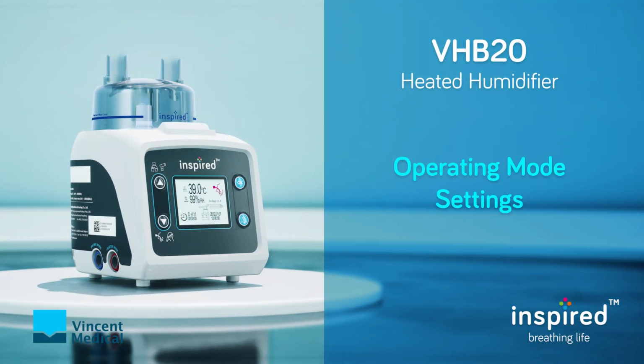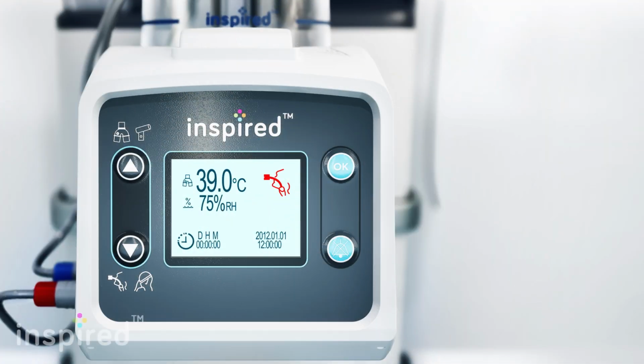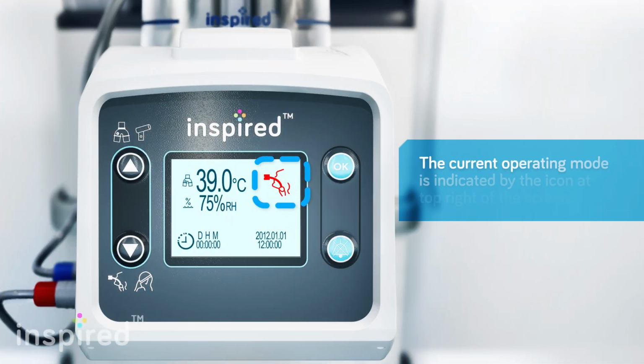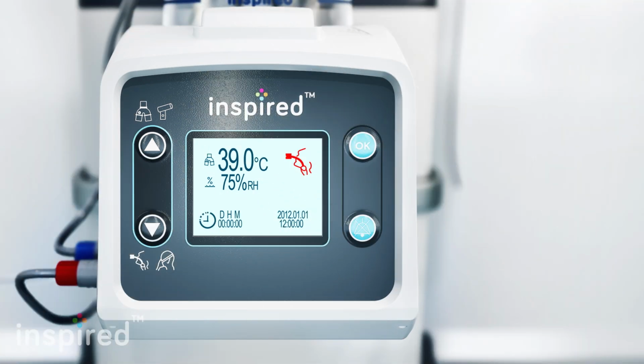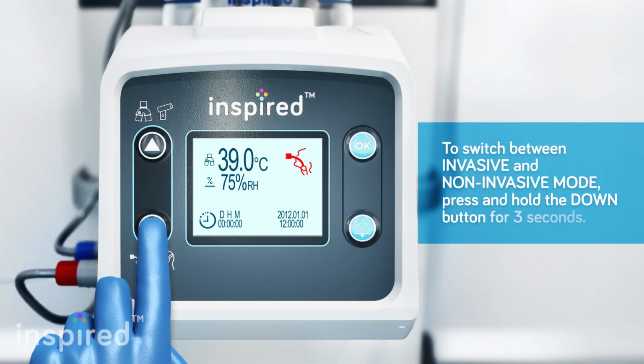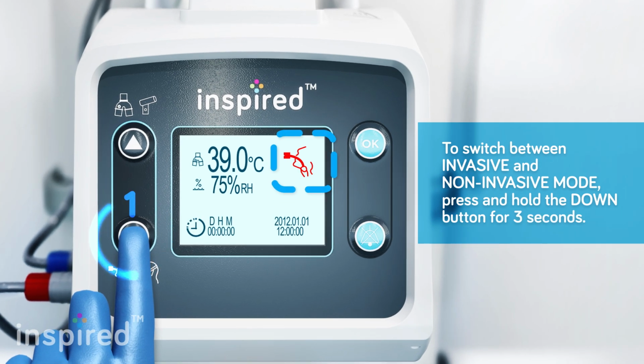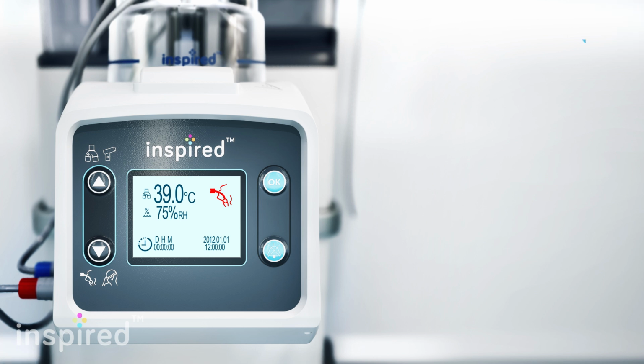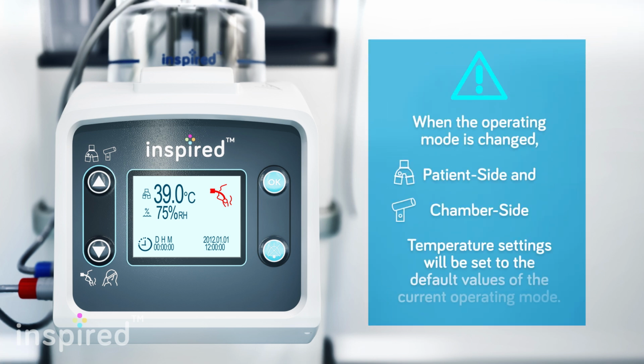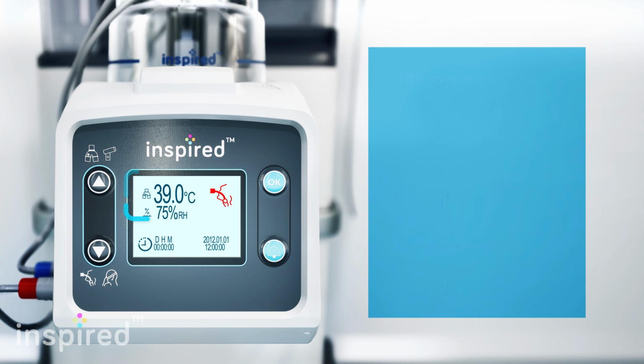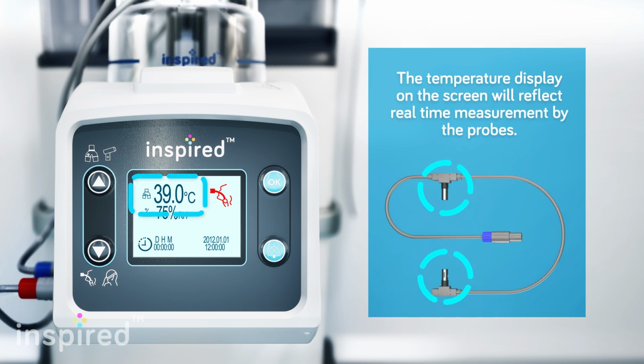Operating mode settings. The current operating mode is indicated by the icon at the top right of the screen. To switch between invasive and non-invasive mode, press and hold the down button for 3 seconds. When the operating mode is changed, the patient side temperature and chamber side temperature settings will be set to the default values of the current operating mode. The temperature display on the screen will reflect real-time measurements by the probes.